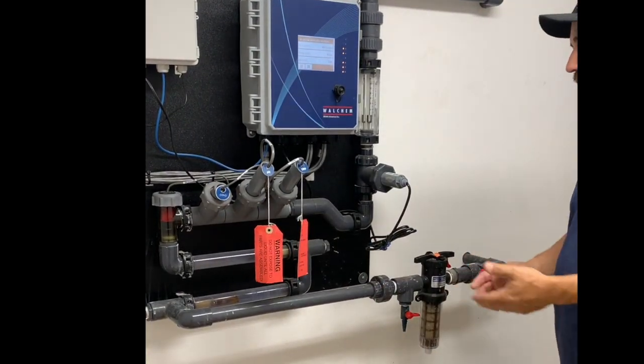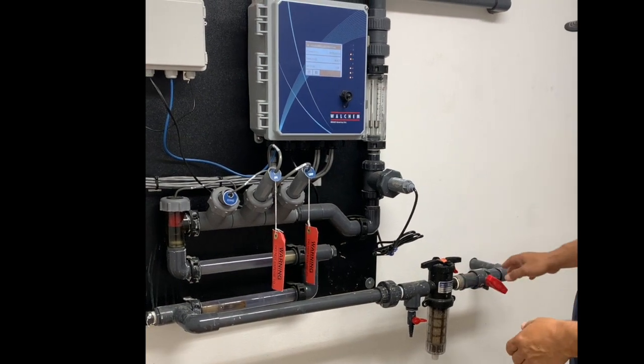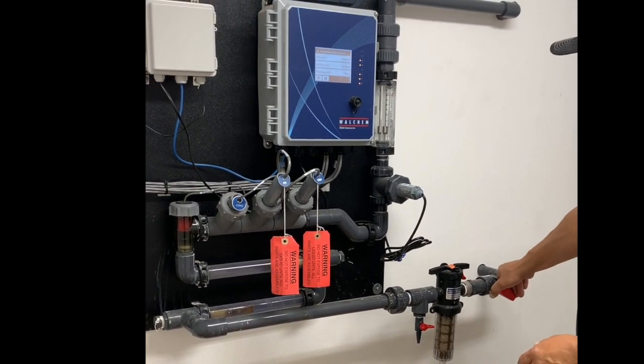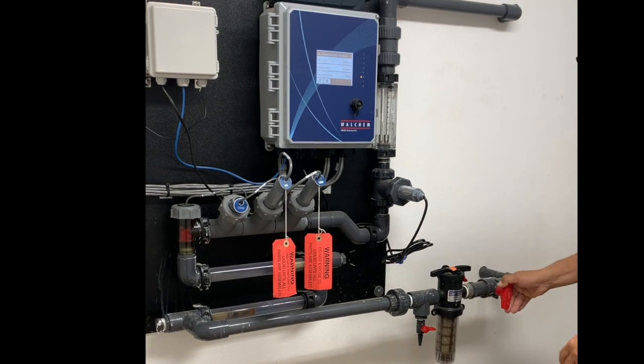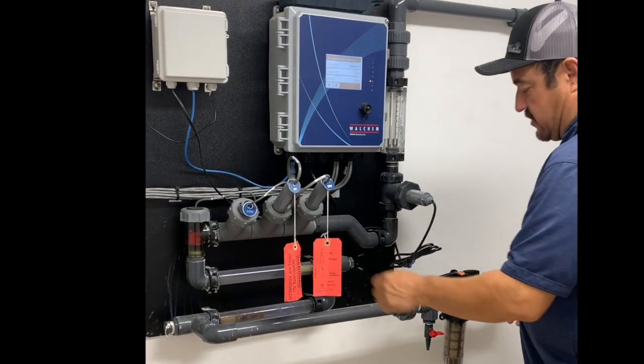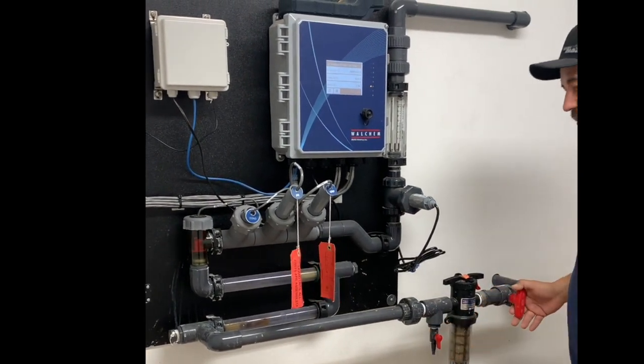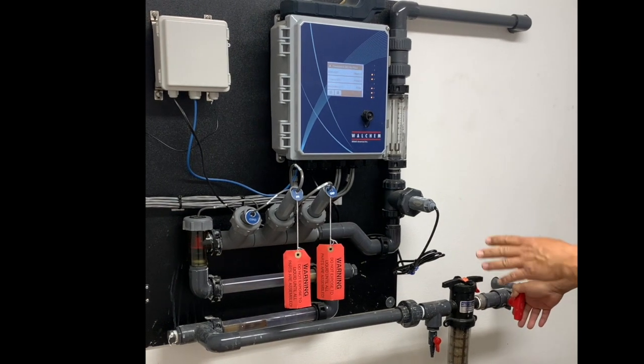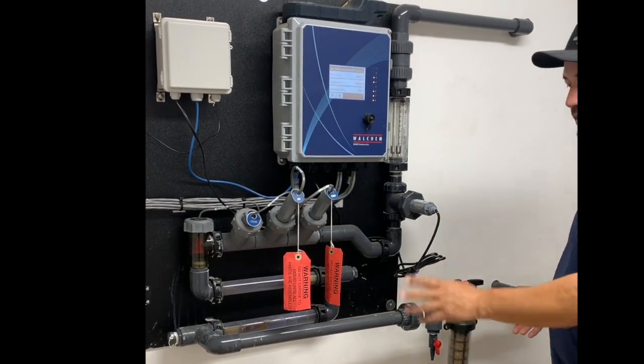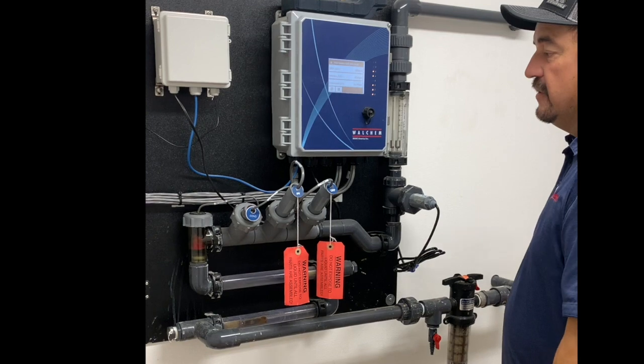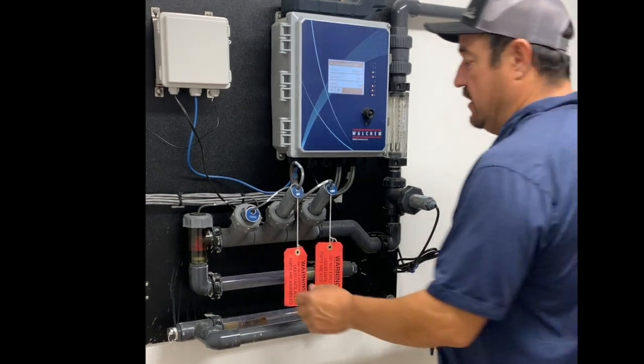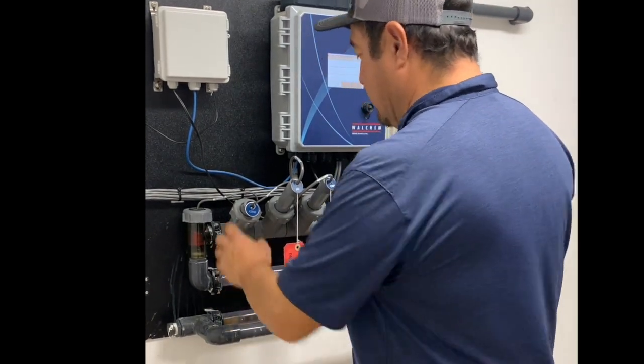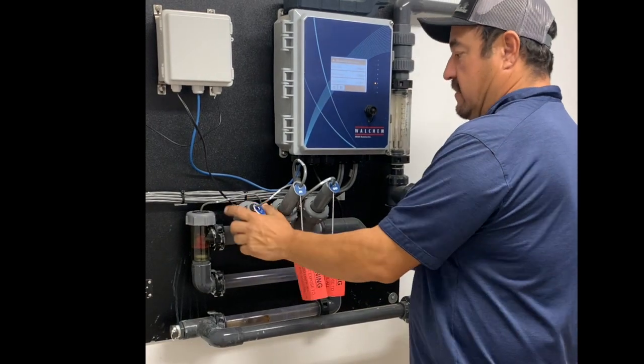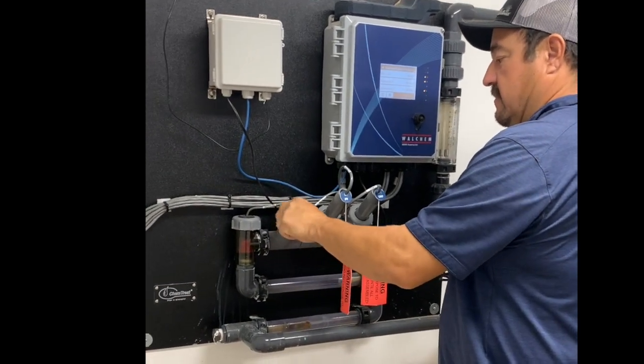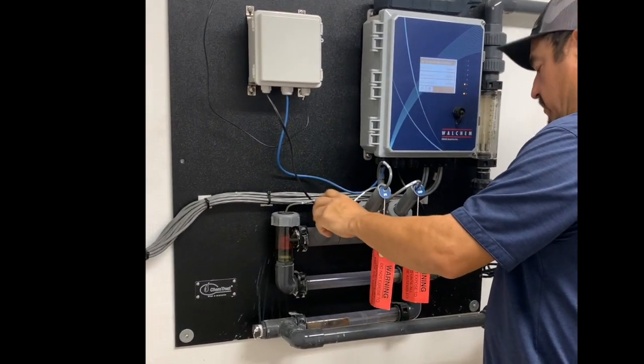So we're going to go in, we're going to isolate the probe right now. We're going to go ahead and shut off the water. Now you still have a little bit of pressure in here, so you want to make sure you release the pressure on the unit so you don't damage the probe and you don't damage anything on the unit itself. So once we've done that, we're going to go in. We're going to make sure that we have taken all the pressure off the unit.